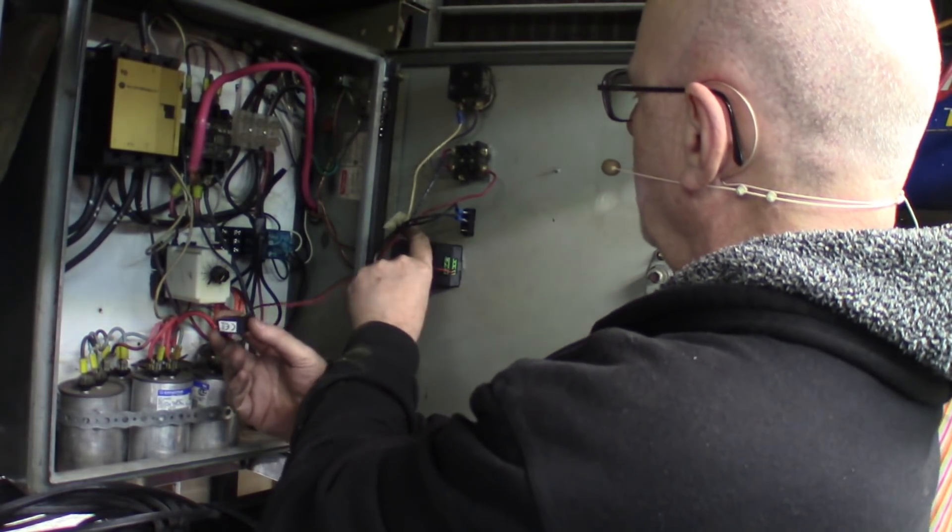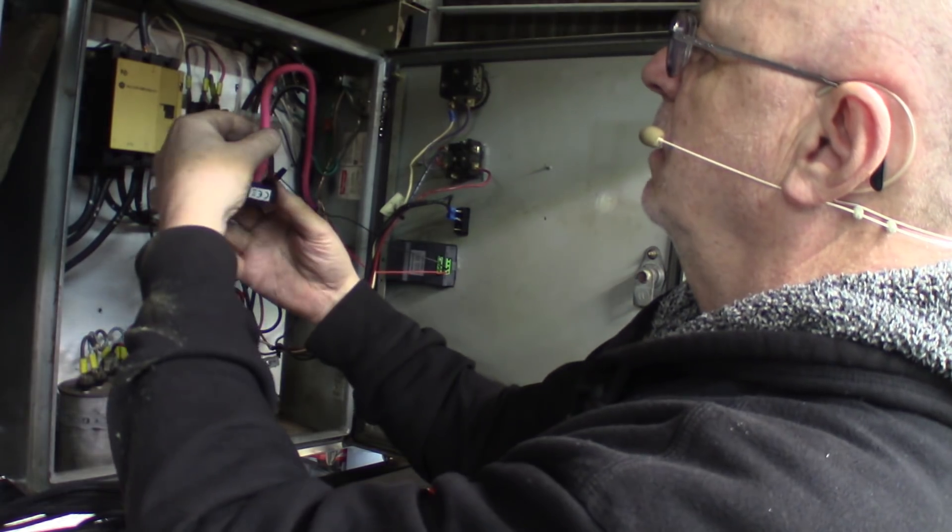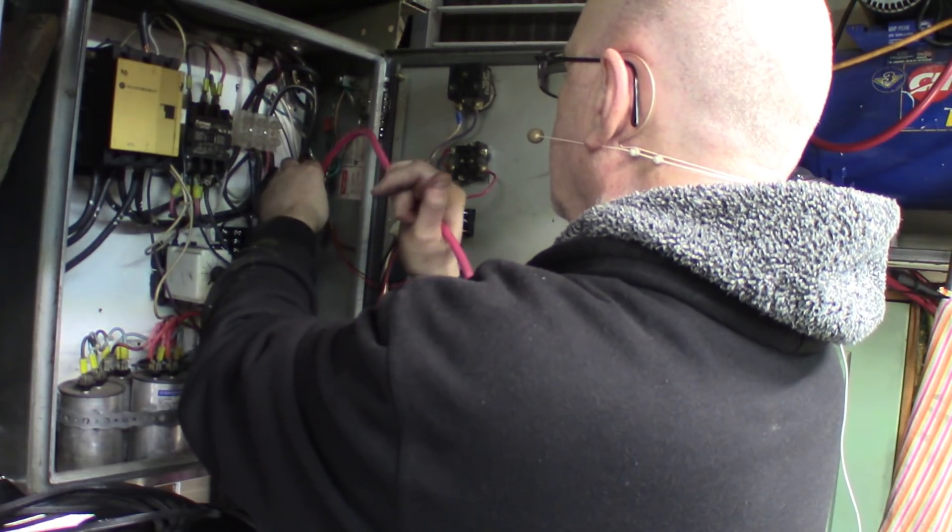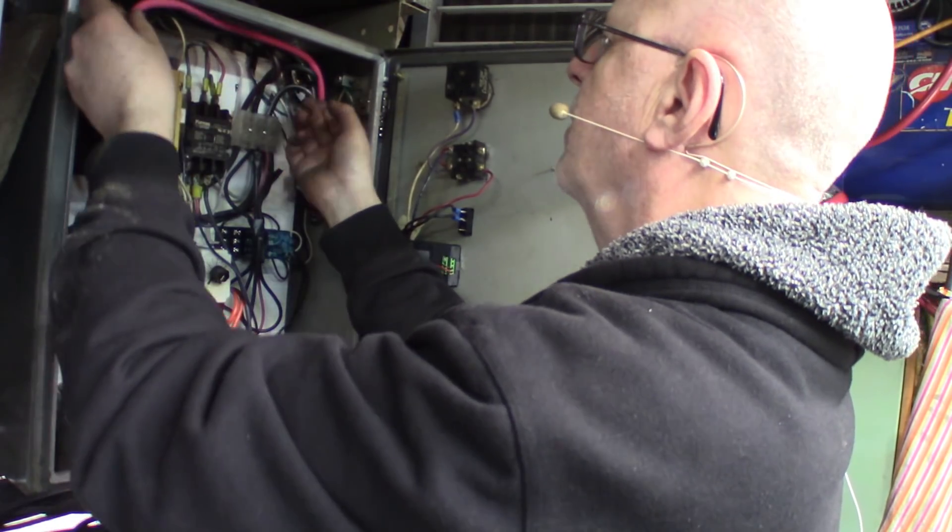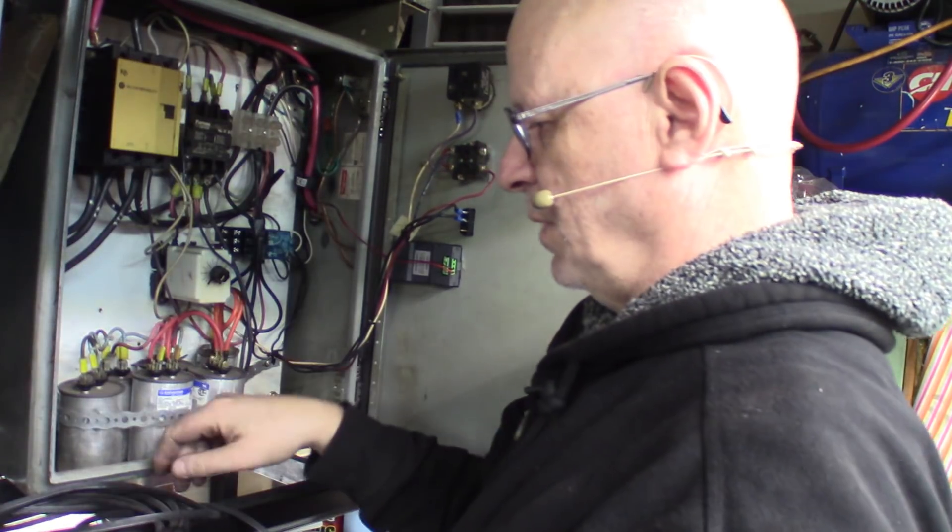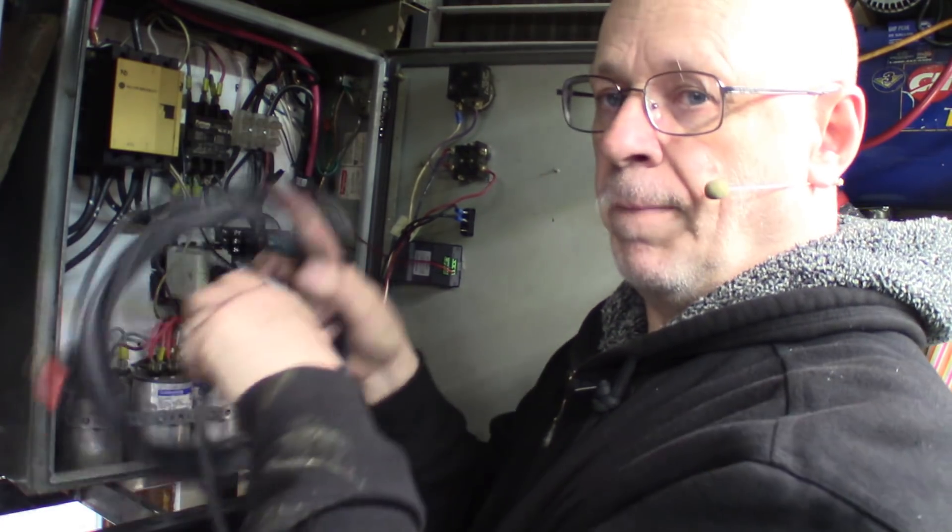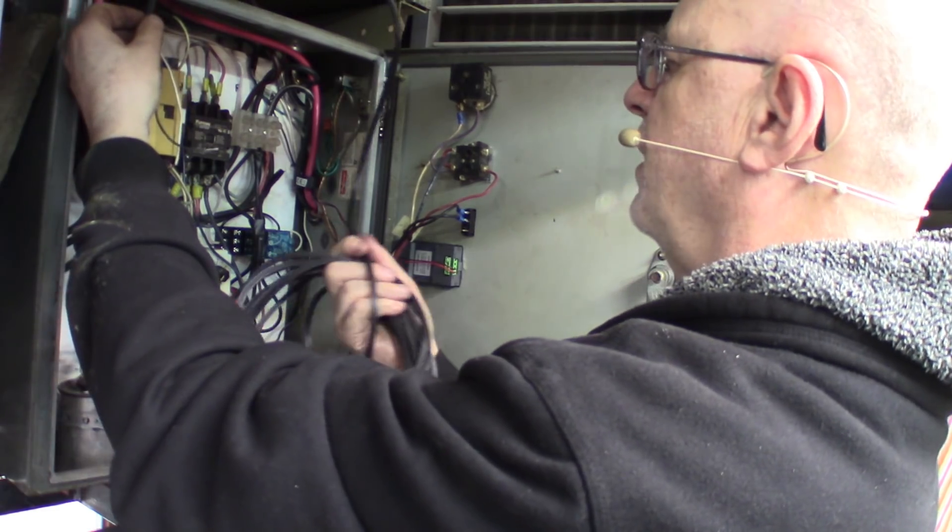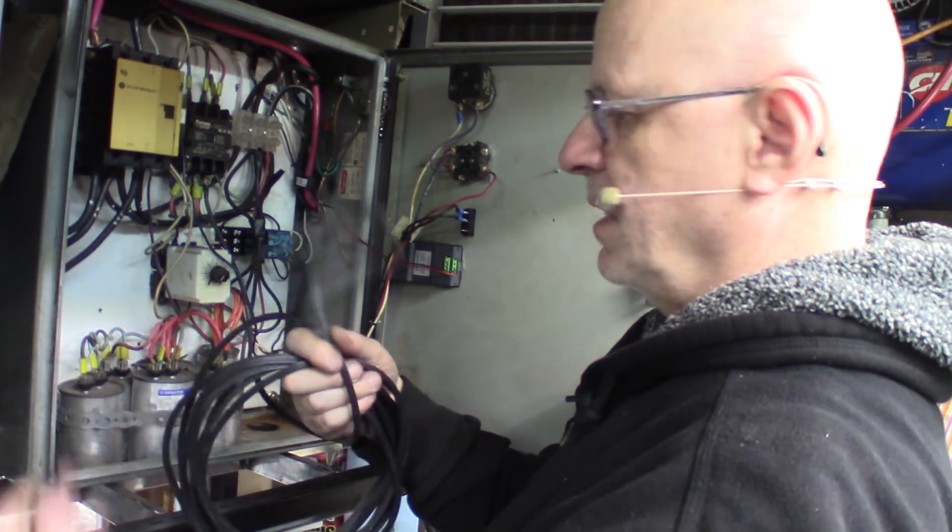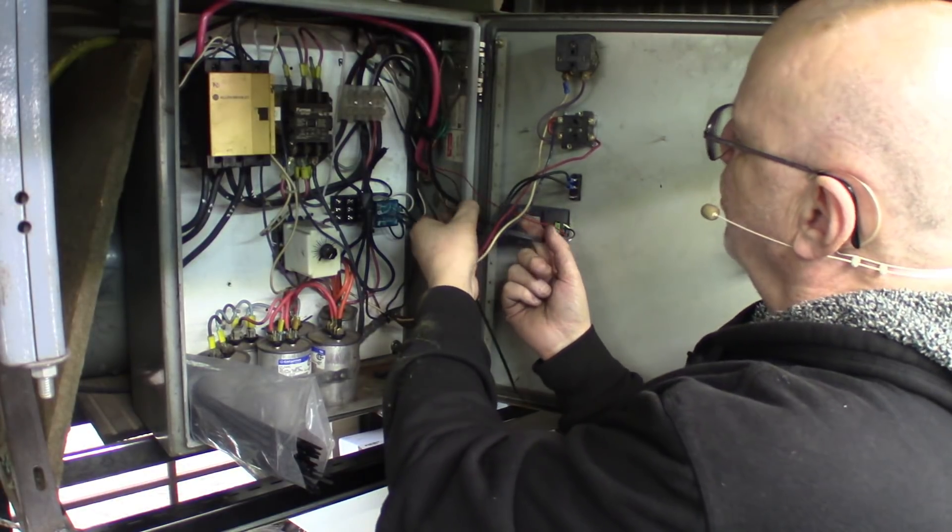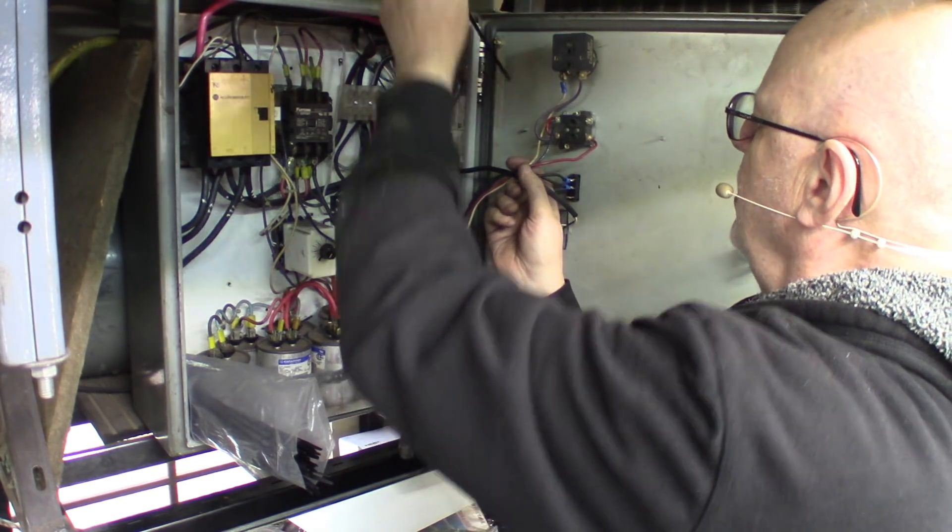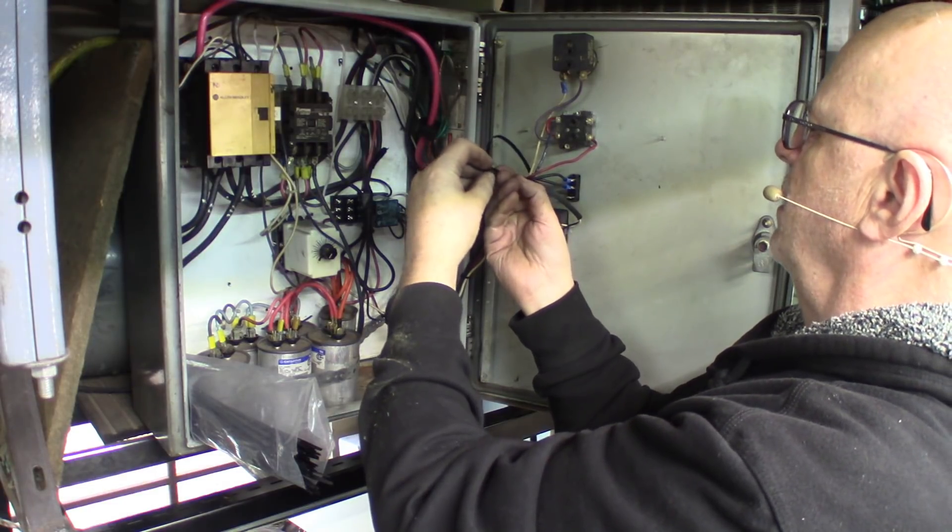So far so good. The box clipped in place. I have to put that ring. That's a coil that measures the current to one of the phases. So this goes right here. I'm going to be putting back this wire into the main relay here. That's pretty stiff wire though. And I'll be connecting this wire here in parallel there to feed this module with 220 volts. So that will be completing the setup. Using a few tie wraps to get this dressed up. I'm not going to stick the sensor wires too close from the other wires in order to avoid inducing interference into it.